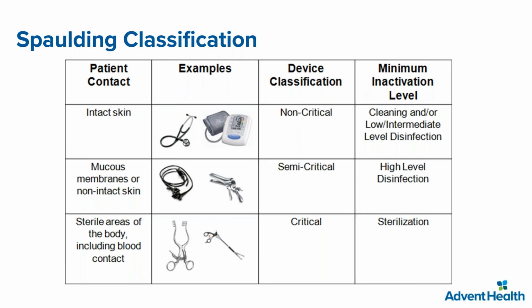You can use a wipe, or you can use whatever product you have in your facility that is in your guidelines. But when we have mucous membranes or non-intact skin, we use, for instance, the endoscopes or the speculum that they use for any kind of vaginal procedure. Those devices are considered semi-critical, and you need high-level disinfection. For speculums, now we have disposables, but if they are not disposable, they can use either high-level disinfection or they can sterilize the item as well. If they are going to enter any sterile area of the body, including having blood contact, then that is classified as critical, and that needs sterilization.